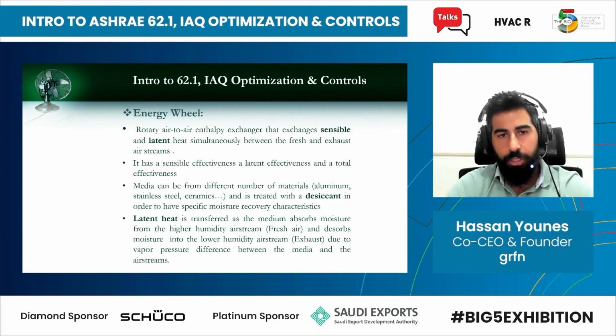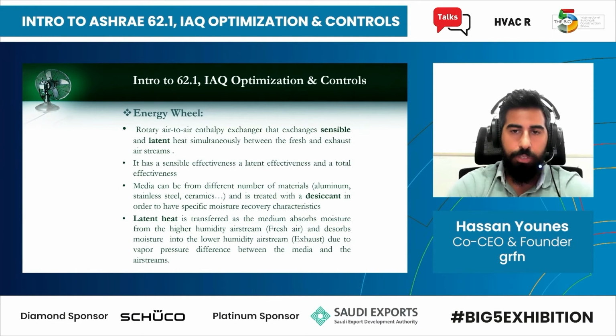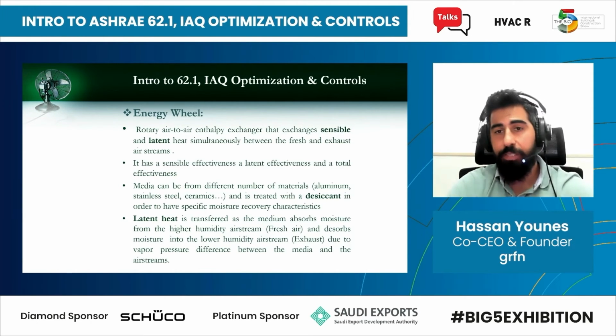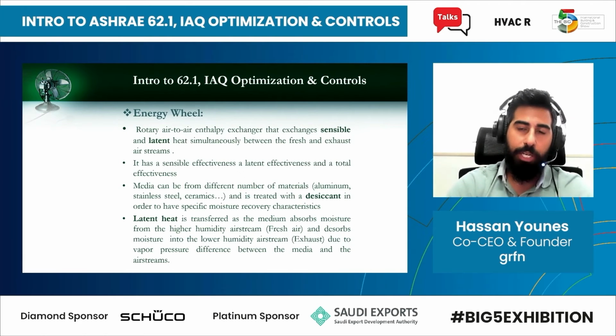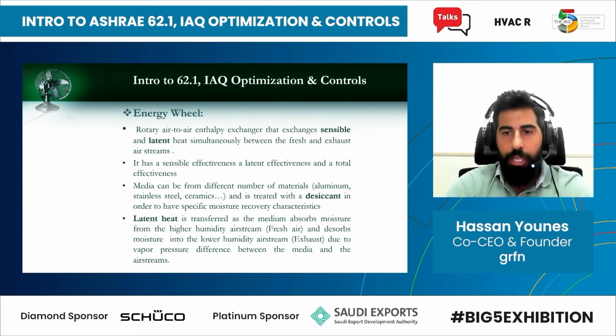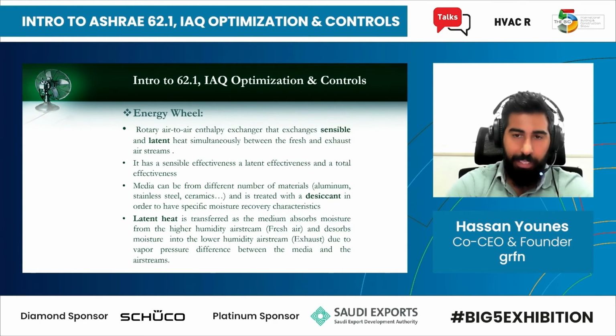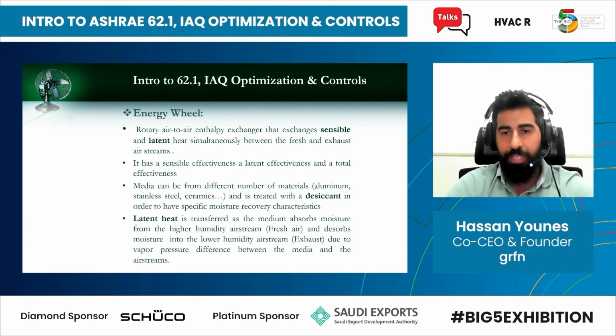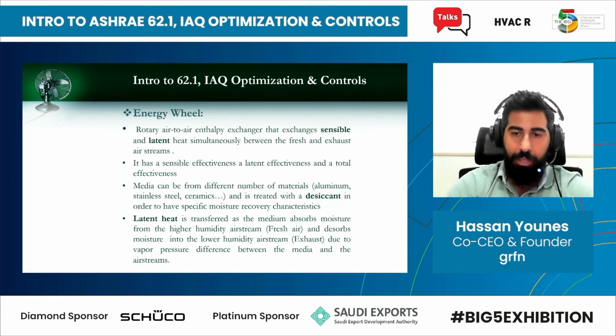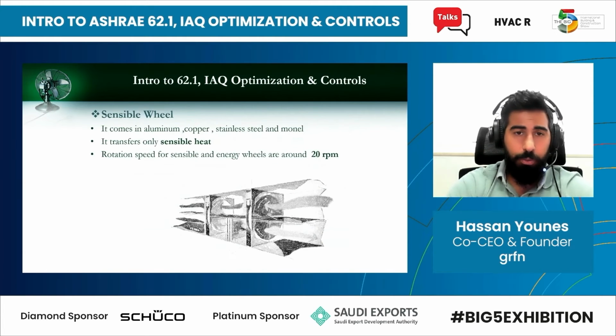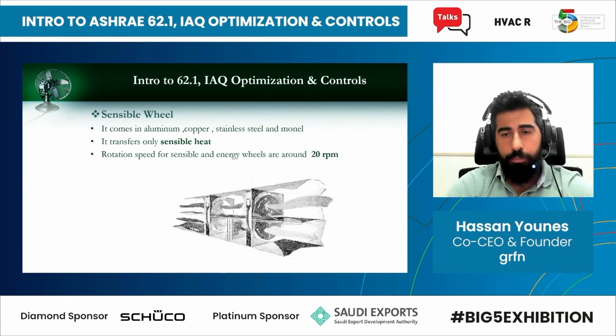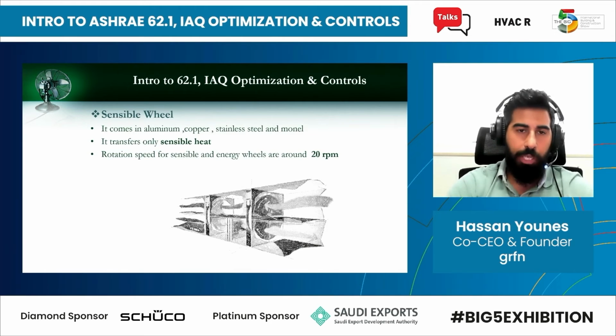So energy wheels are rotary air-to-air enthalpy exchangers that exchange sensible and latent heat simultaneously between the incoming outside air and the exiting exhaust air. It has a sensible effectiveness and a latent effectiveness, so it can cool and dehumidify the air. Normally, there's a type of desiccant on the wheel that can suck out the humidity from one side and send it to the other side, which is the exhaust. You have other types, like plate heat exchangers, that could also be used. But normally, in general, we use heat recovery wheels.